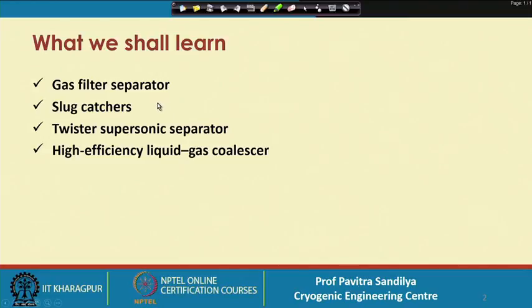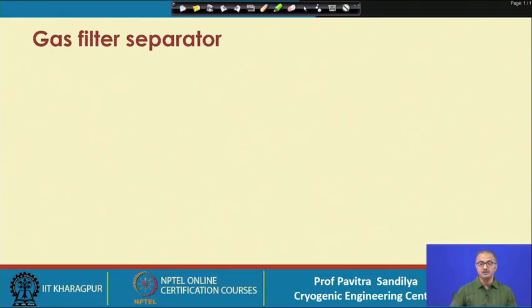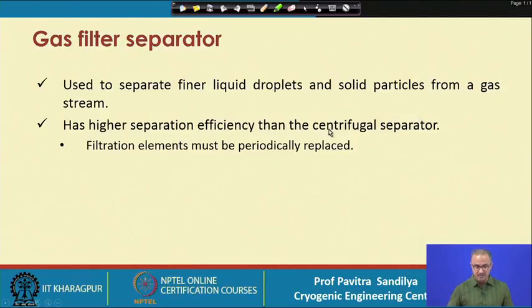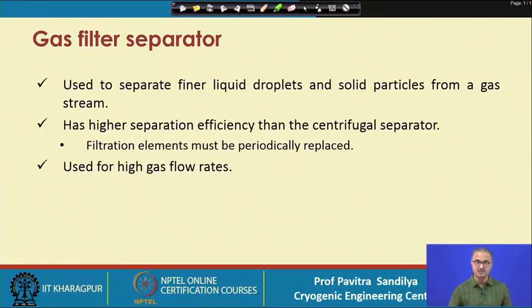In this lecture we shall be learning about some other separators: gas filter separators, slug catchers, the twister supersonic separator, and high efficiency liquid gas coalescer. The gas filter separator is used to separate finer liquid droplets and solid particles from the gas stream, and these have higher efficiency than the centrifugal separator. However, the filter element must be replaced from time to time because the pores get clogged and no more fluid can pass through. This kind of separator can be used for high gas flow rates.